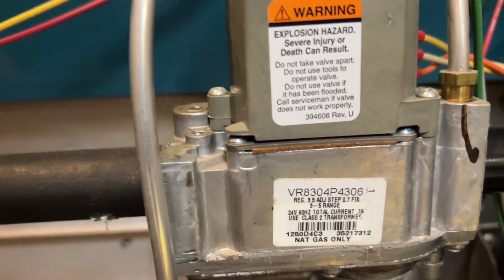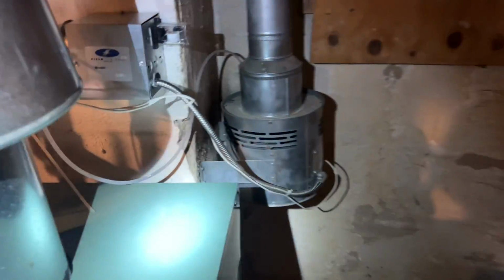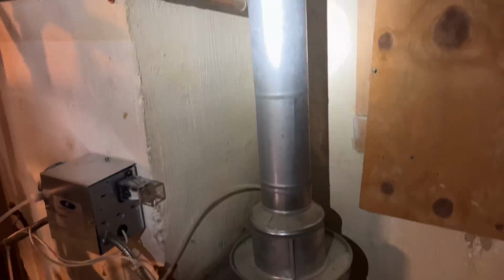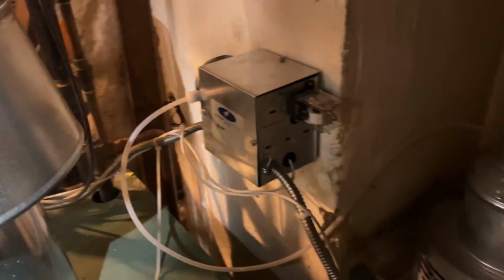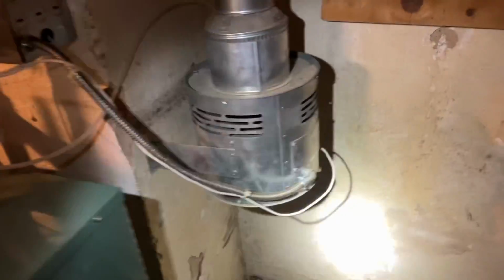Okay, one of the things that turned on is this doodad. This is by Field Controls. This is called Fan in a Can. This brings in fresh makeup air. It looks like it's coming from all the way down there, all the way from outside, in 4-inch, single wall flue pipe. We have a control, a pressure switch. It gets wired to both boilers. And it brings fresh makeup air. It looks like it's been replaced once before already.